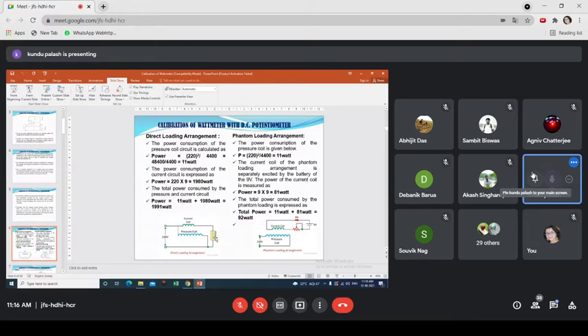So under rated conditions, the pressure coil, or voltage coil, of the wattmeter is excited with a fixed voltage, which should not vary. Only the current coil should vary in a calibration circuit, so that under rated condition, that is full load condition, there will be a certain amount of power consumed by the load. So the power to be delivered by the source is equal to the total power, part of which is consumed by the load and part of which is dissipated due to electrical loss. That is very high, so the power supply rating would have to be very large.